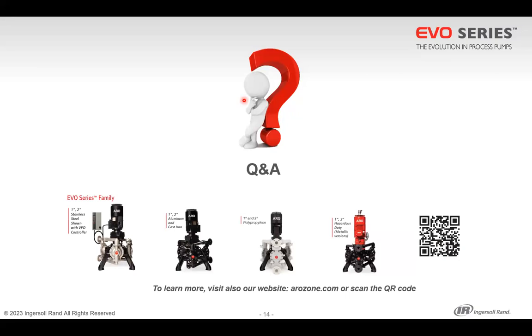Now, it depends if you can use more than one pump for this. But if you really need to move such an amount of powder, probably a powder pump is not the right system. But in terms of type of powder, if it's a very light, polymeric powder, I cannot guarantee, but there are some good chances that you can use the powder pump. Now, in terms of quantity, we are really out of our range.